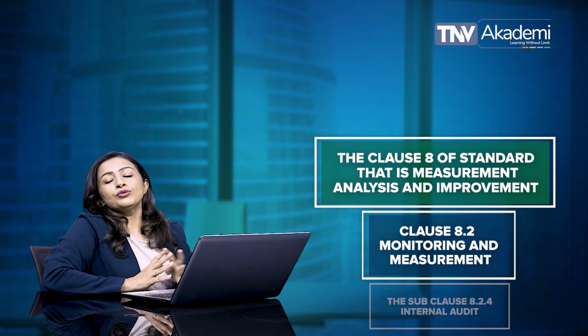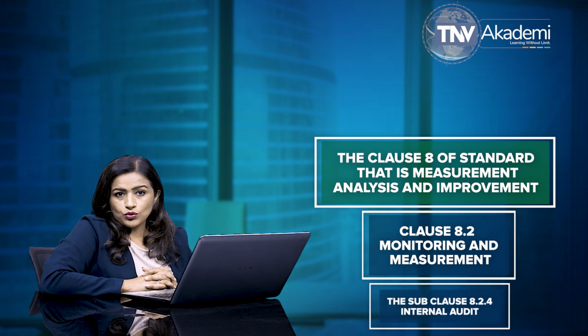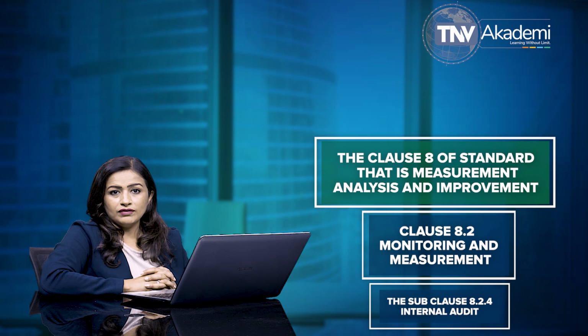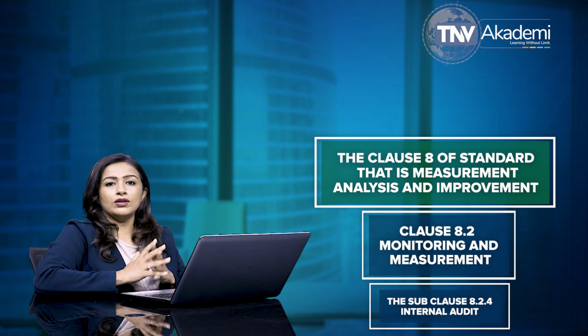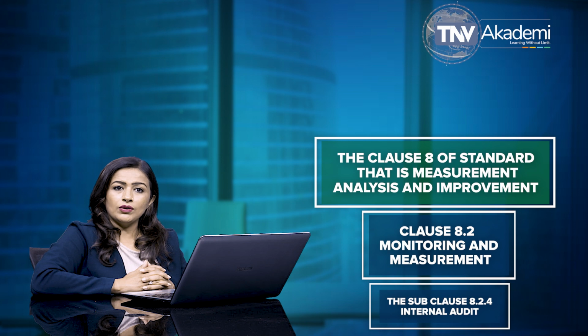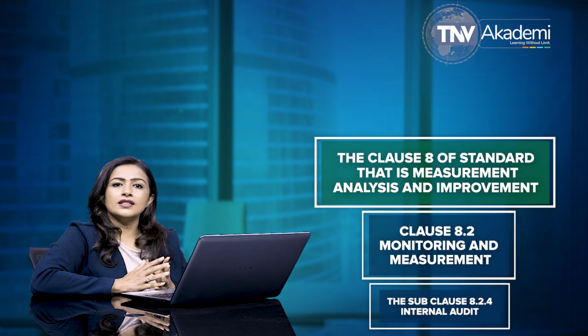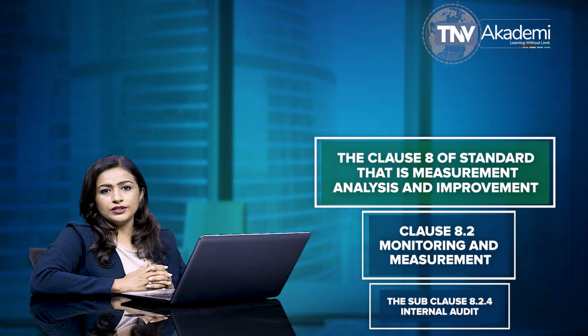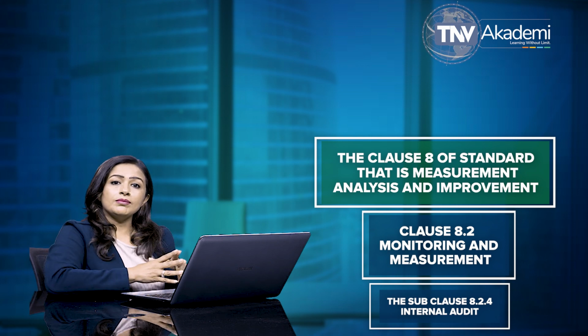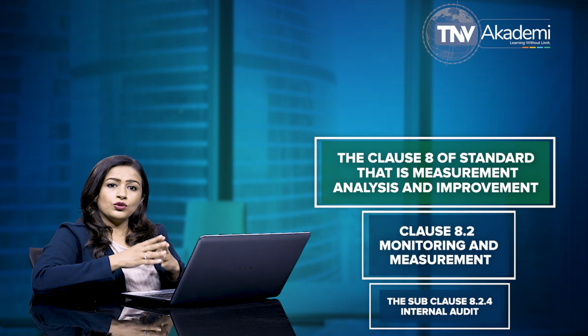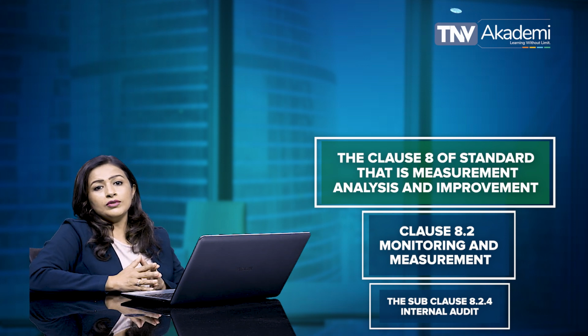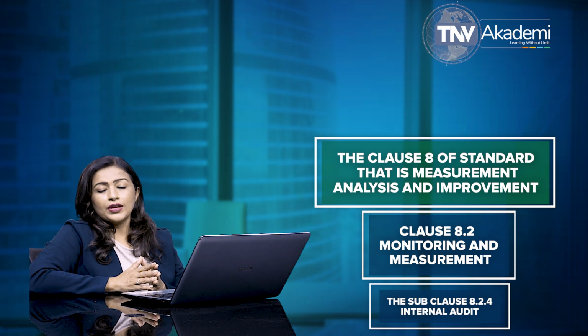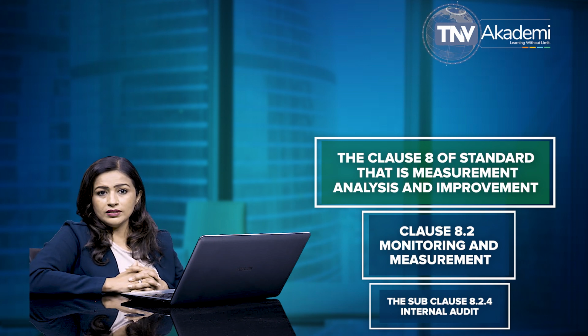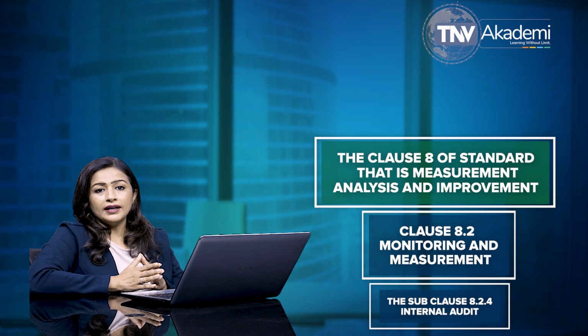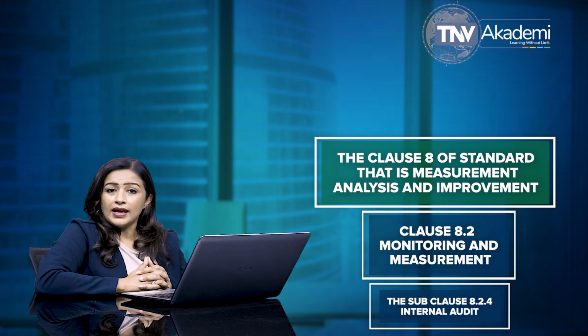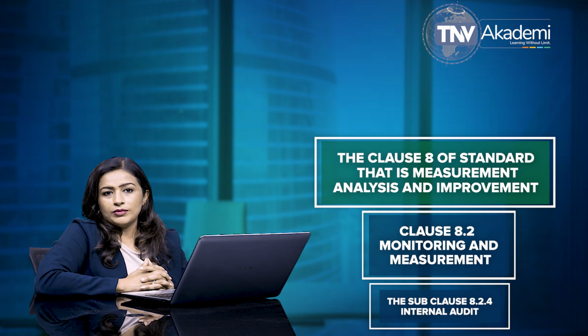Now, let me come to the subclause 8.2.4 of ISO 13485:2016, that is internal audit. According to this subclause, the organization is required to conduct internal audits at planned intervals to determine whether the quality management system conforms to planned and documented arrangements, requirements of this international standard, quality management system requirements established by the organization, and applicable regulatory requirements.